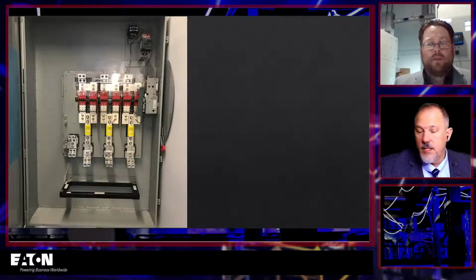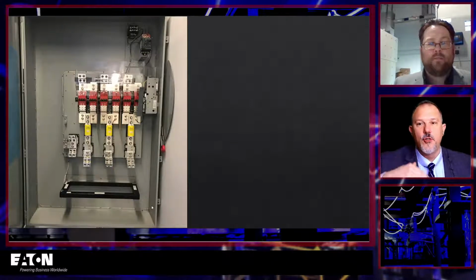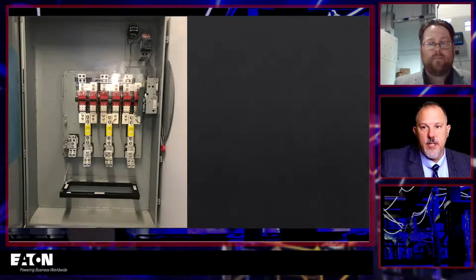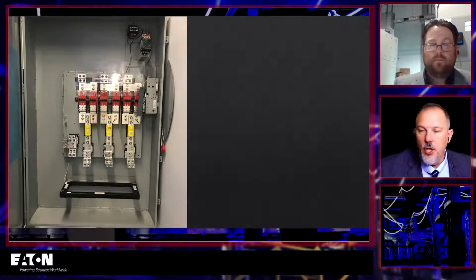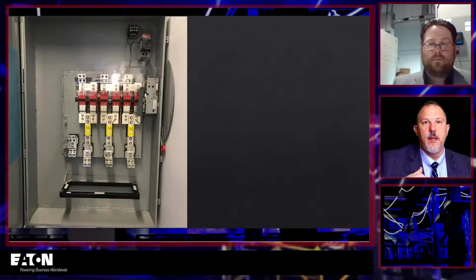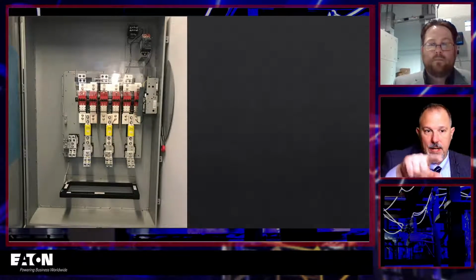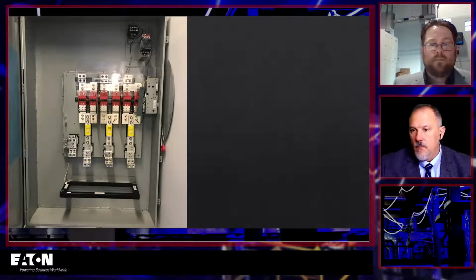This is just a picture of a zero sequence CT that's mounted down below, and actually it should be up above. It'll depend upon your source, where your source conductors are coming from, whether they're fed from the bottom or from the top. Obviously you want the CTs on the line side of the fusible switch. And in this case, we had to move that CT up.